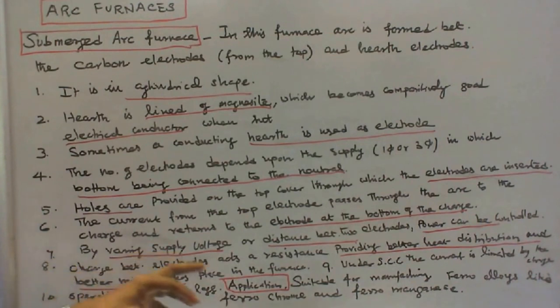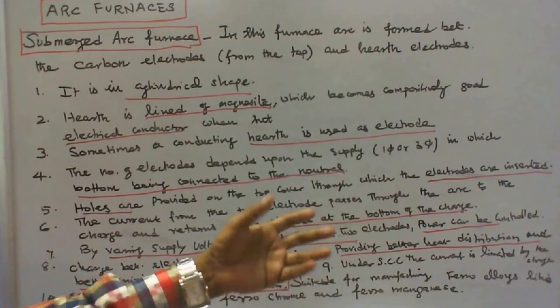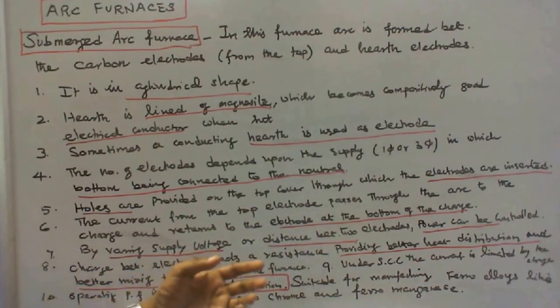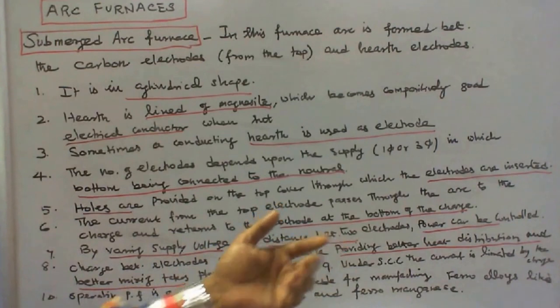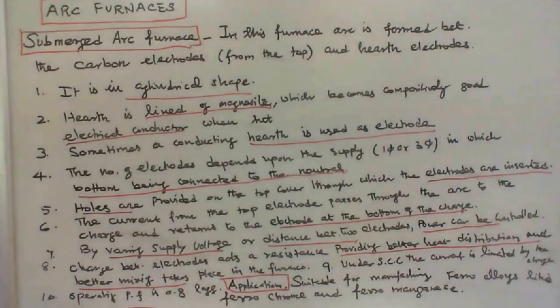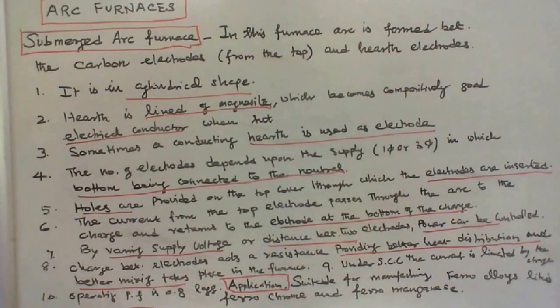By varying supply voltage or distance between two electrodes, power can be controlled. Charge between electrodes acts as a resistance providing better heat distribution and better mixing takes place in the furnace. Under short circuit condition, the current is limited by the charge itself. Its operating power factor is 0.8 lagging.